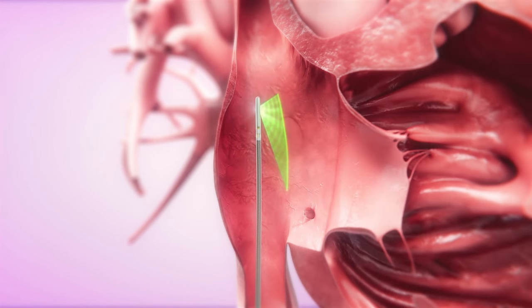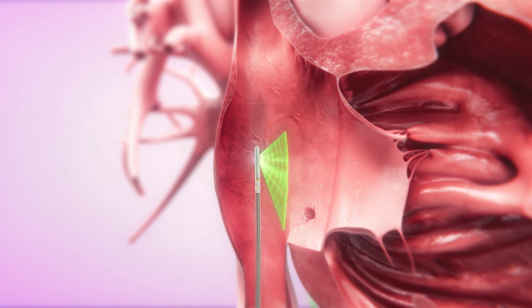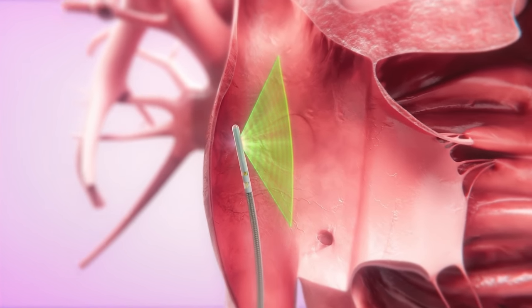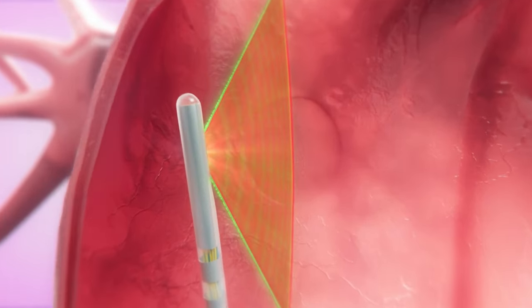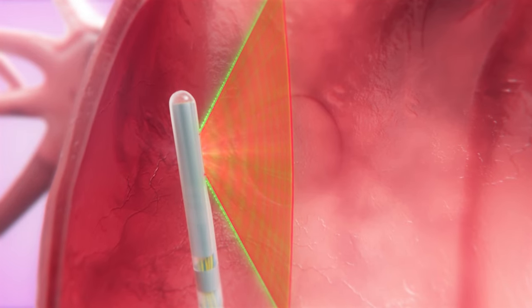Aligning the catheter on the fossa ovalis ensures the best angle for optimal left atrial appendage imaging. Advanced 3D capabilities enable digital steering and X-plane, providing twice the information in the same amount of time.